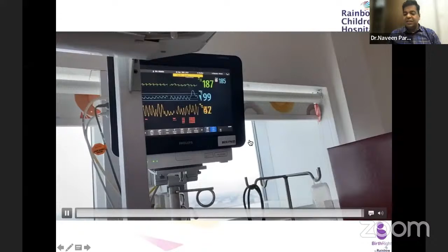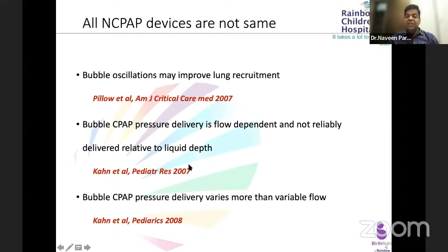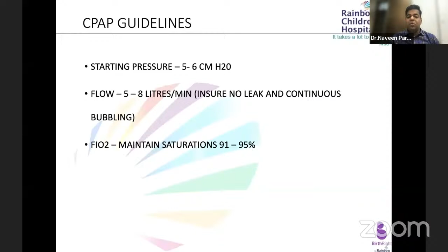Okay. So all devices are not the same. When we talk about bubble CPAP, bubble oscillations may improve lung recruitment. There was a suggestion that in bubble CPAP, because of the oscillations generated, they may improve gas exchange better. Bubble CPAP pressure delivery is flow dependent and not reliably related to the liquid depth. So we have seen that bubble CPAP pressure delivery varies more than the variable flow. When we talk about the CPAP guidelines, it remains a mystery how much pressure to start. The majority of units start at a pressure of 5 to 6 centimeter of water. The flow rate which is put is 5 to 8 liters per minute. We should ensure no leak and continuous bubbling, and the FiO2 to maintain saturation is between 91 to 95%.